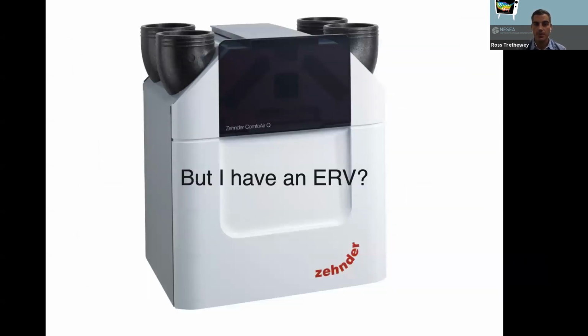The common solution that people always tell me is, it doesn't matter, I have an ERV, right? I have an HRV or an ERV. That's going to solve it, right? That's my makeup air. And that's not actually the right way to think about it. ERVs or HRVs are balanced ventilation machines. They bring the same amount of air out of the building as you bring into the building. So if I have a 100 CFM ERV, it's bringing 100 CFM out and bringing 100 CFM in. It's balanced, meaning it has no effect on the pressure of the building.